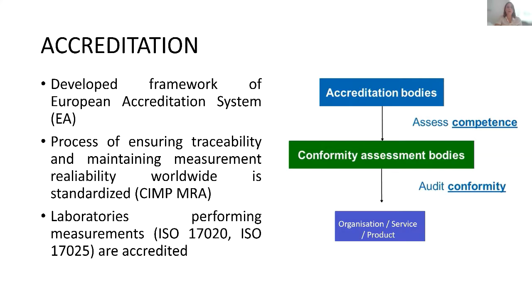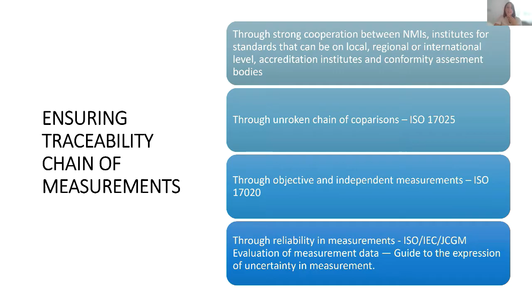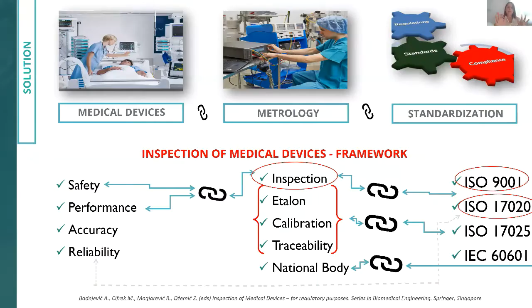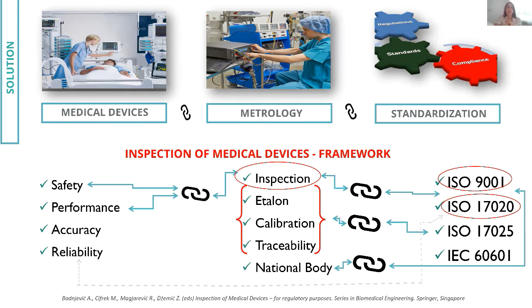Calibration of etalons used by the inspection body is performed according to ISO 17025, and all other relevant standards in the field of medical device performance and safety were used for the definition of conformity assessment rules. As a result of an inspection, you have a pass or fail conclusion. If the device complies with the set technical criteria during the inspection, it is marked as pass. If any parameter is out of the specified range, that device is marked as fail. This is the overall look of the legal metrology framework. Again, I'm emphasizing this is being used in Bosnia and Herzegovina, and from this framework we are actually collecting the data. That is how this is connected together.